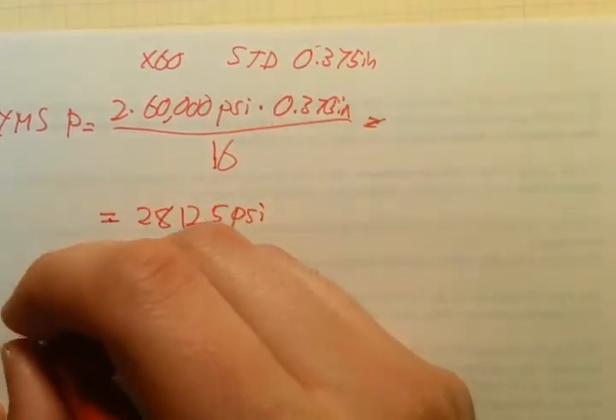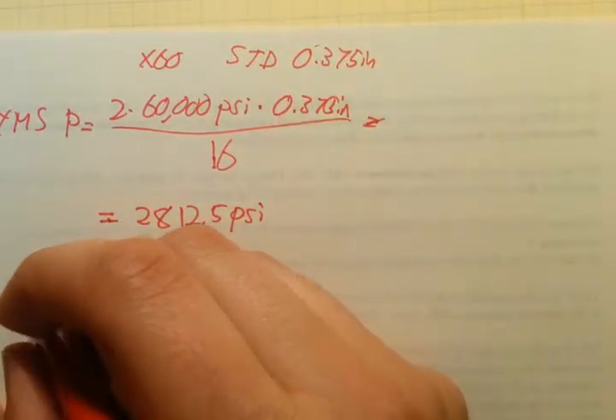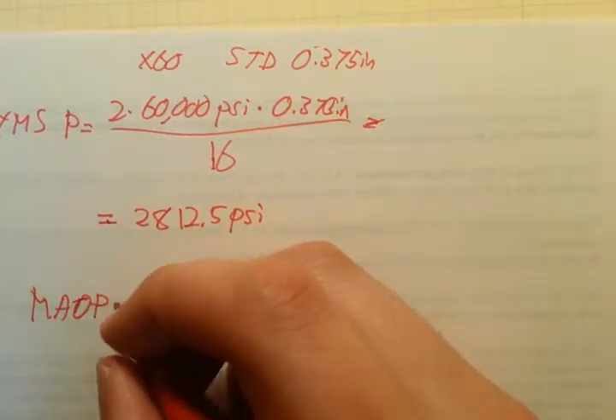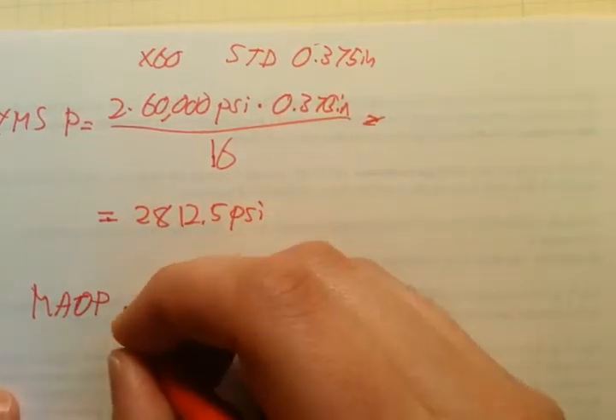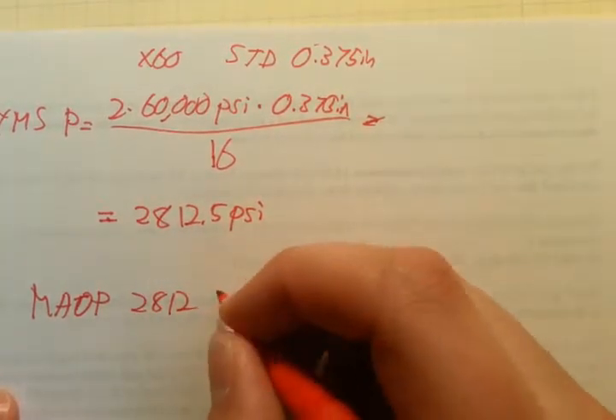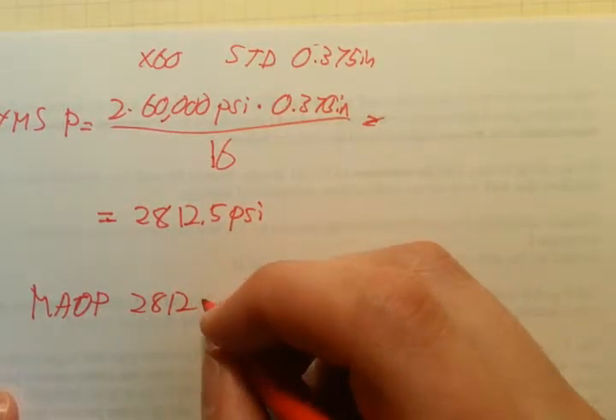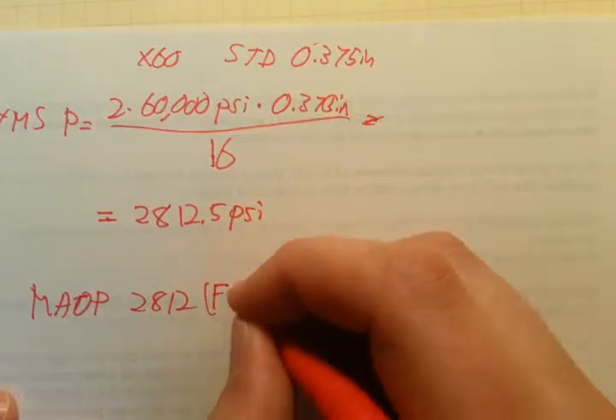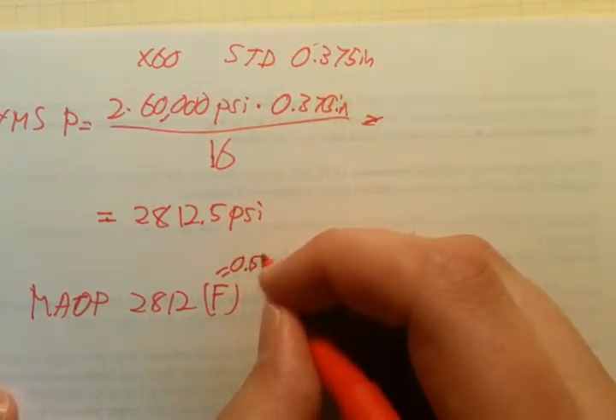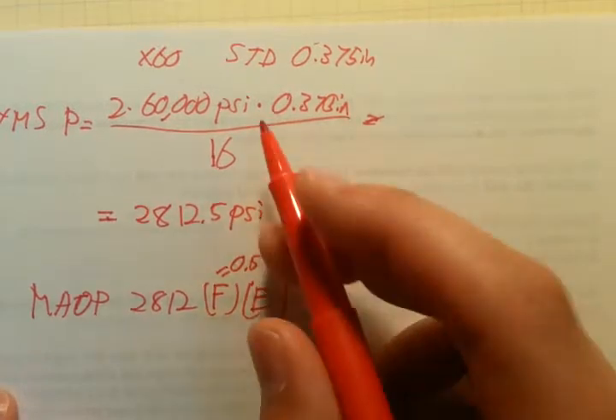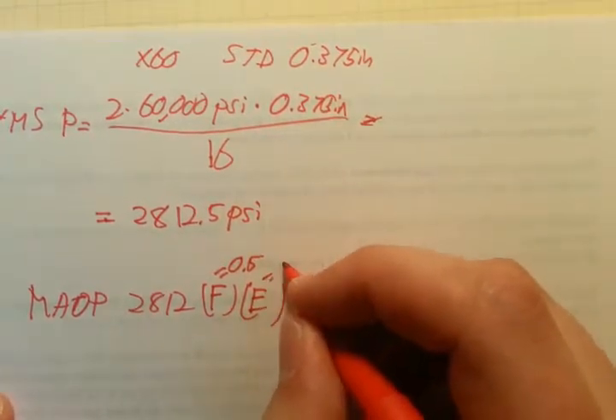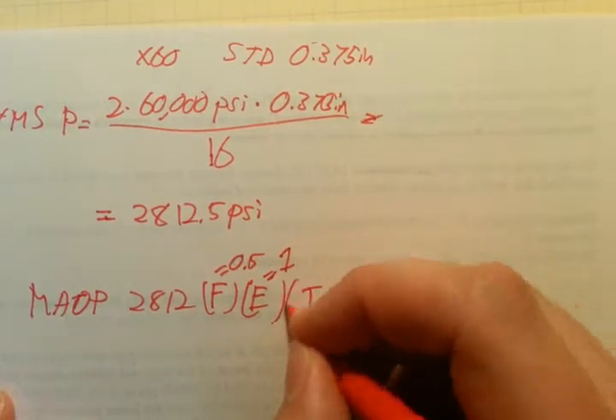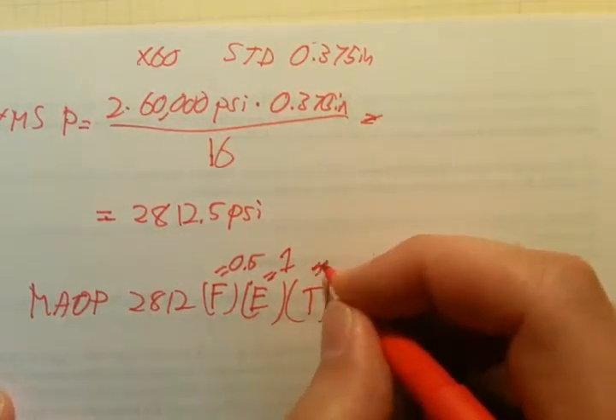So to get our MAOP, maximum allowable operating pressure, we're going to take that and multiply it by our three different safety factors. F, since it's class 3, is 0.5. E—it's newer pipe, they're calling it X60, so we don't have to worry about it—we're going to leave it as one. Same thing with T; we weren't given a temperature.